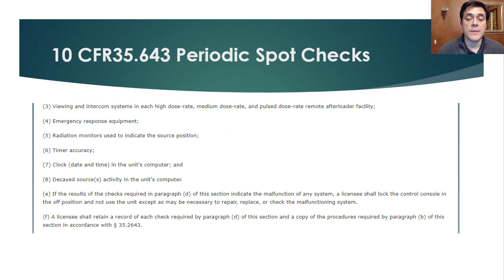The viewing and intercom system needs to be checked to make sure that you can see and hear everything going on in the room. The emergency response equipment needs to be checked for consistency, and it needs to be present. And the radiation monitors used to indicate the source position, including the independent monitor if you happen to have an independent monitor. The timer accuracy needs to be within a second, and the clock, date, and time in the unit's computer needs to be verified. This date and time check is to assure that any decay correction is within a reasonable amount of percent dose delivered.